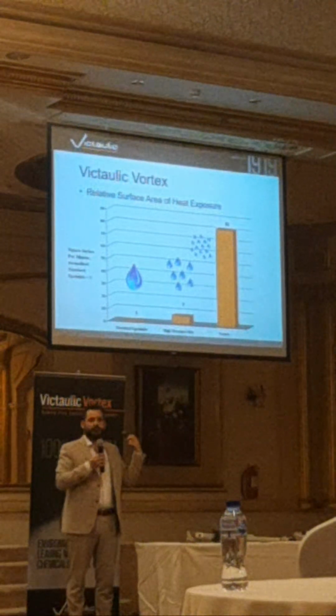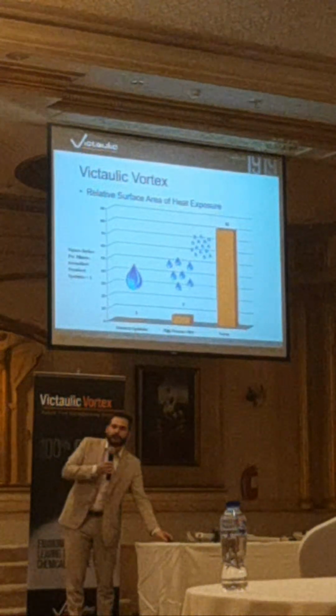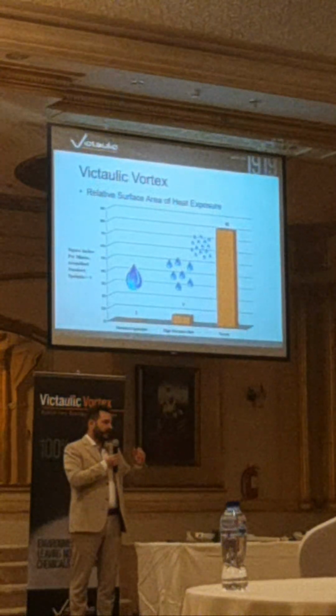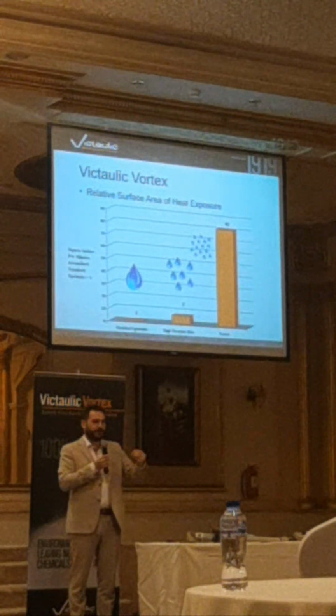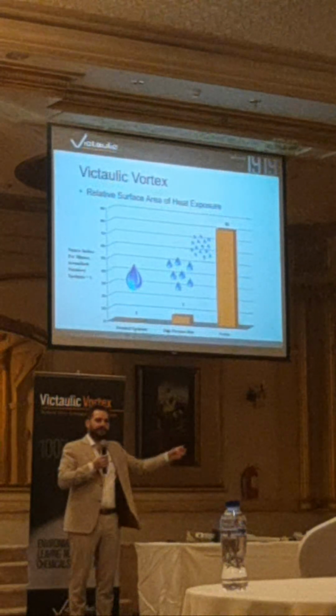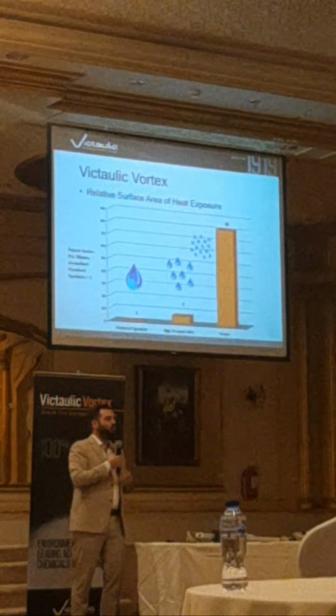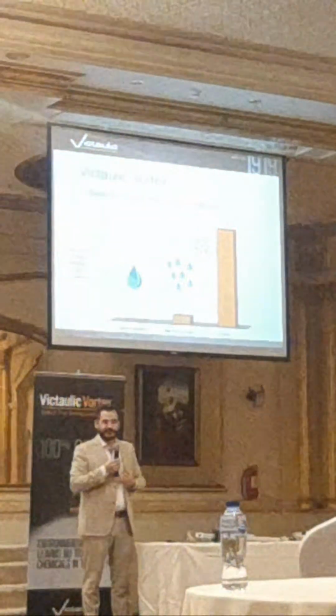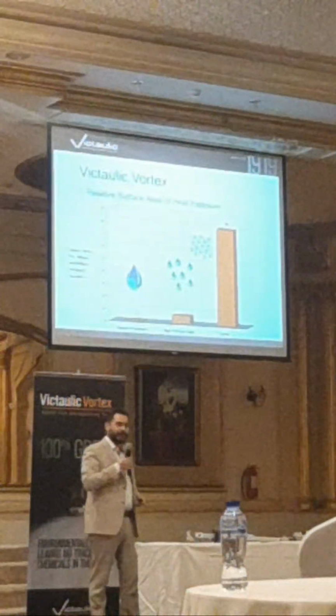This is similar to how a vortex system works. Because we're using a small volume of water made into a very fine mist, we cover the fire from all sides, taking heat away much more efficiently compared to a sprinkler system or a water mist system. Usually I do the comparison in the hall where I'm standing.